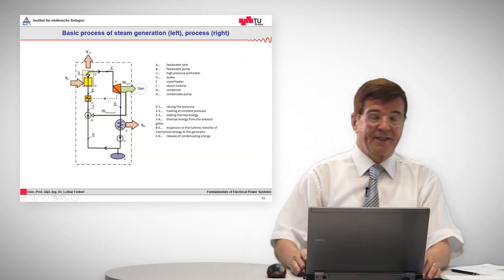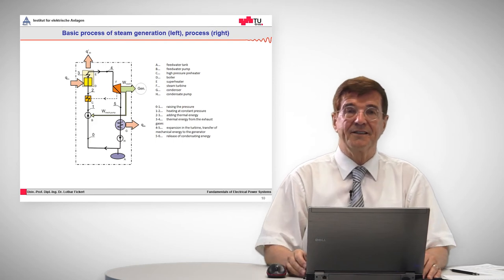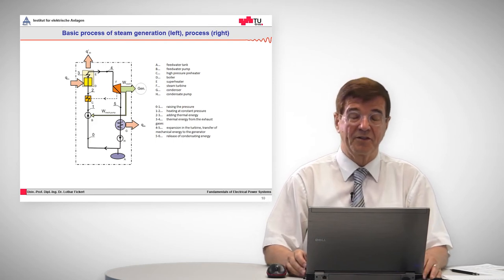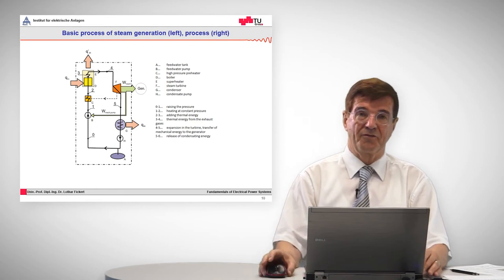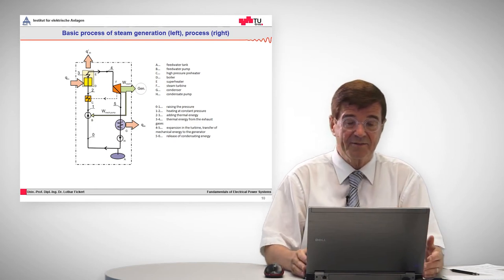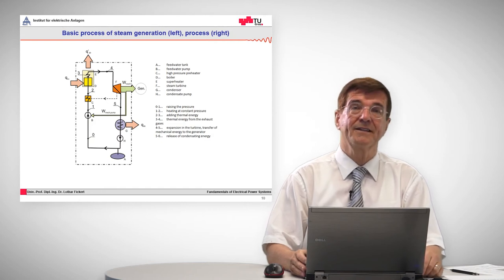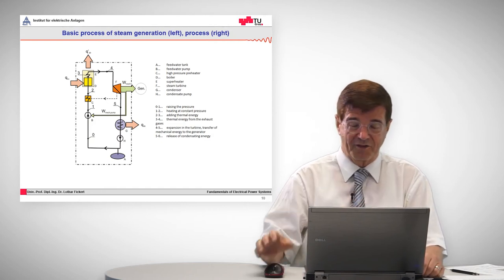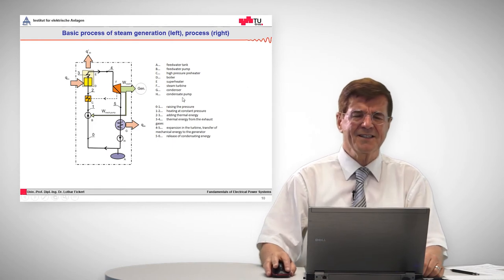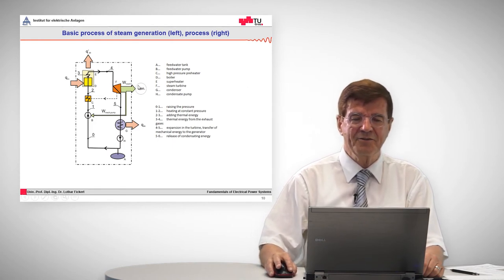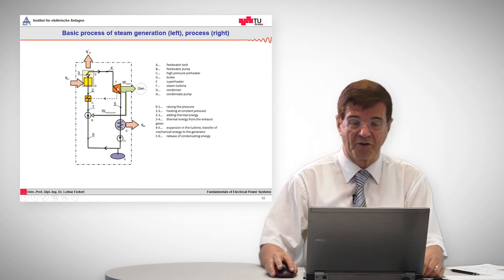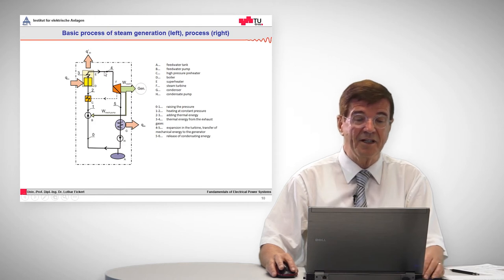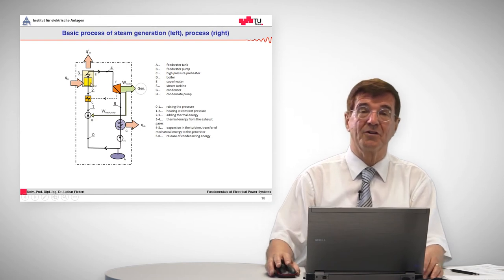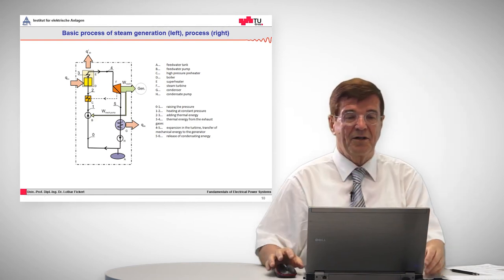Now, when it comes to bioenergy conversion, this is mostly done in a thermoelectric process. So that means the biomass is burned, and while it's burnt, it produces heat. The heat is converted into steam, and the steam is converted into electrical energy. But basically, it's the same principle. Let's start from the generator. The generator gets its power from the turbine. The turbine gets its power through this steam duct from the heater, the boiler. The boiler is the equivalent of the upper basin in the hydraulic power station.